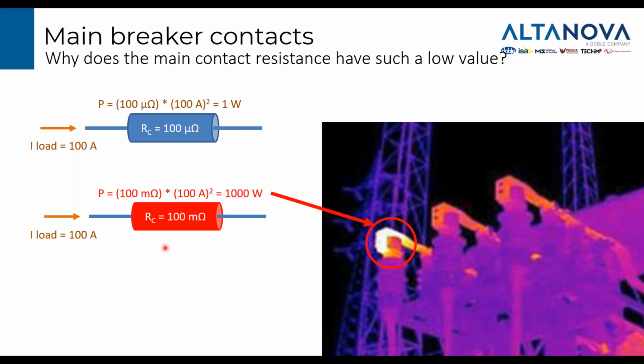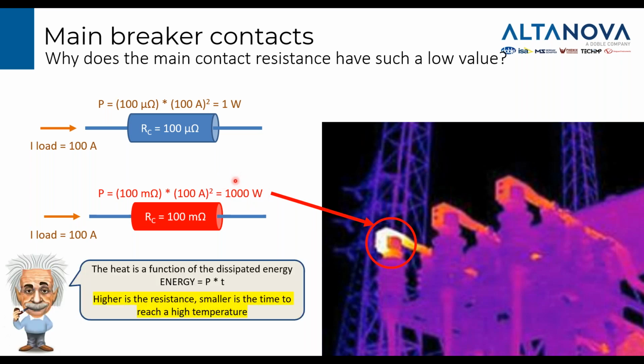But if something happened to the contact, and the resistance value increases, for example if the value goes up to 100 milliohms and the load current remains the same, the dissipated power is in the range of 1000 watts. We have in our houses ovens and hair dryers that can dissipate more than 1000 watts, and we know how much heat they can produce. So this condition cannot remain for a long time.